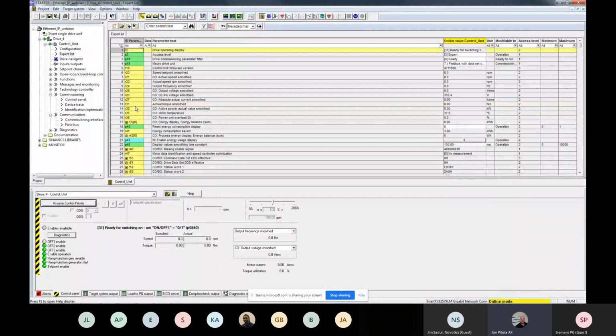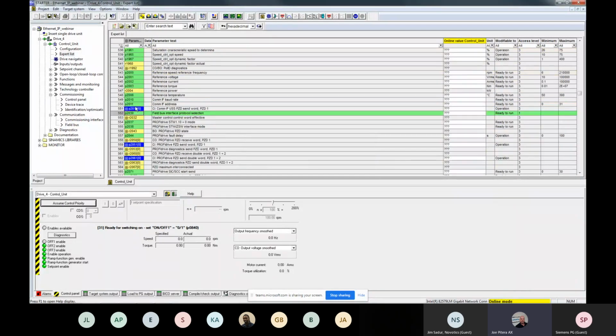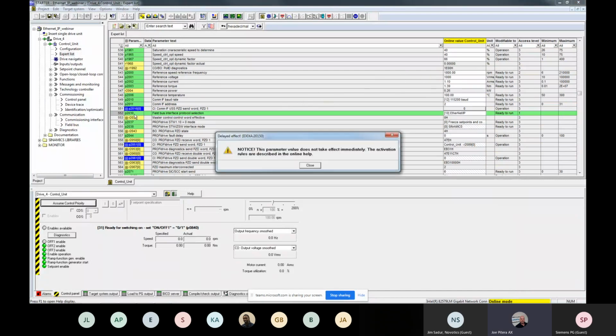So in this case, it's parameter 2030. I mistyped it, 2030. Here it's selected for Profinet. I'm going to drop down the box and go to Ethernet IP. Here it gives you a pop-up saying that the value does not take effect immediately. The activation rules are described in the online help. This usually only happens after a power cycle.